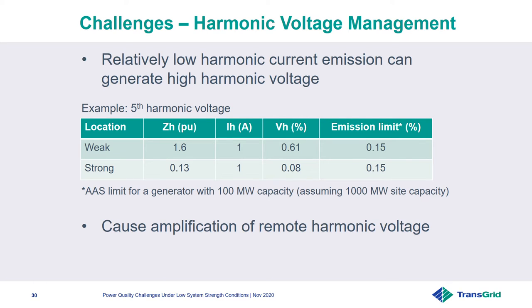So, when the harmonic impedance is high, relatively low harmonic current emission can generate high harmonic voltage. An example is given here. As you can see, 1 ampere of 5th harmonic current can generate 0.61% 5th harmonic voltage at the weak transmission bus, whereas it is only 0.08% at the strong transmission bus. For comparison, the emission limit for 5th harmonic voltage for a 100 megawatt plant is given in column 5. This clearly demonstrates the challenges that a generator to be connected at a weak transmission location will face in complying with power quality technical requirements. Further, high harmonic impedance can cause amplification of remote harmonic voltages.